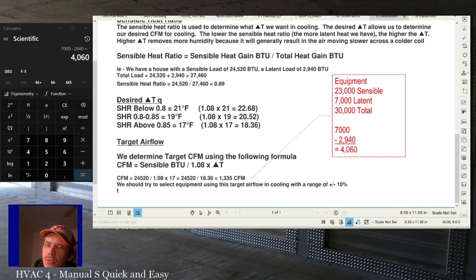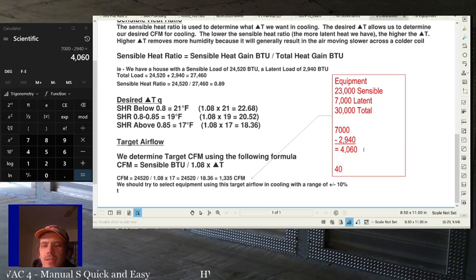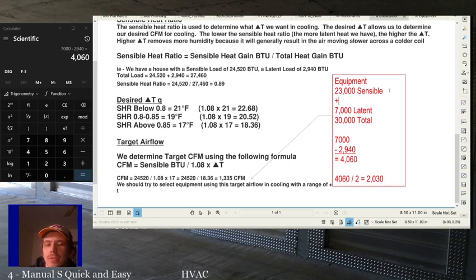The problem is we can't use all of it because ACCA won't let us. And really, those BTUs are geared towards latent removal. They're not geared towards sensible removal, right? But what we can do is take that 4,060 that we have left over and divide it by 2, okay? And that'll give us 2,030. That 2,030, half of the excess latent, is what we can add to our sensible, right? So we can add that 2,030 to our sensible.